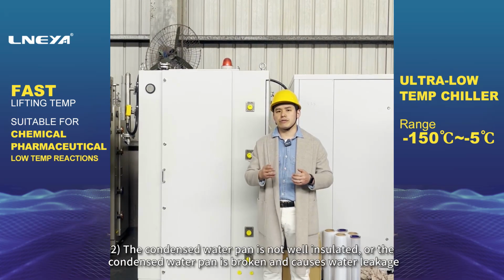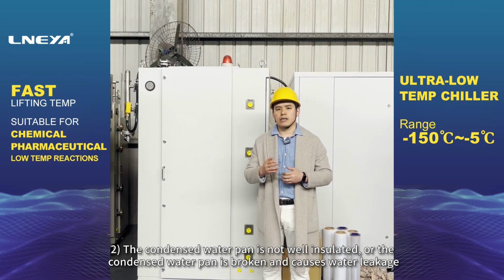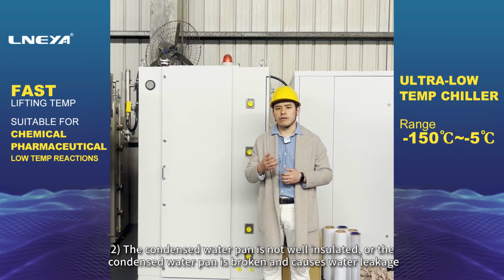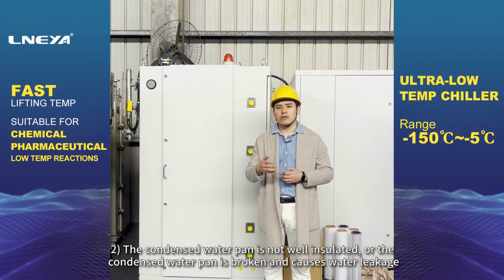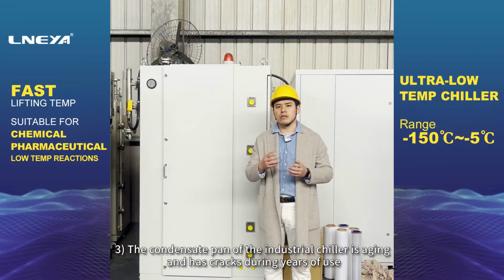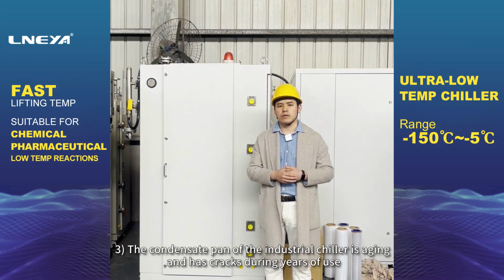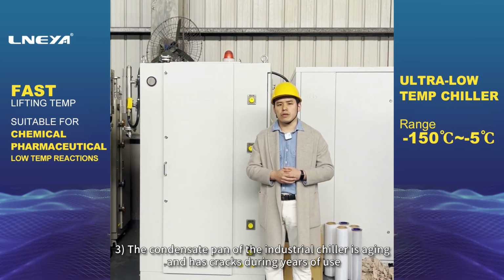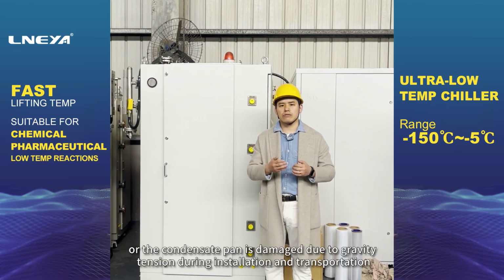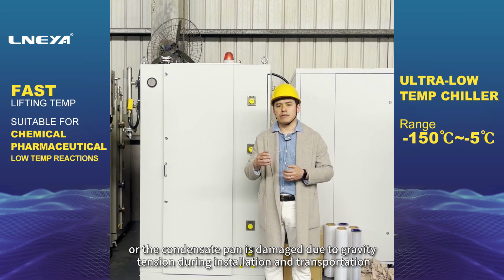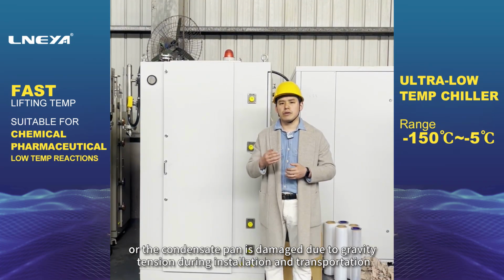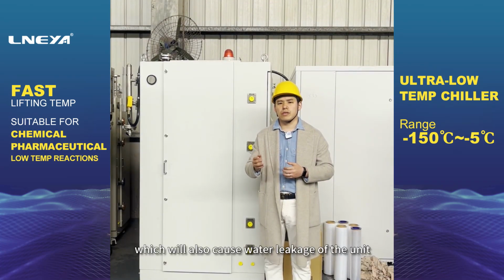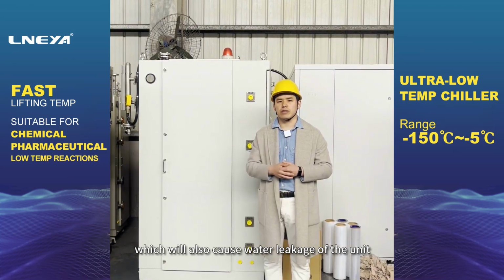2. The condensed water pan is not well insulated, or the condensed water pan is broken and causes water leakage. 3. The condensate pan of the industrial chiller is aging and has cracks during years of use, or the condensate pan is damaged due to gravity tension during installation and transportation, which will also cause water leakage of the unit.